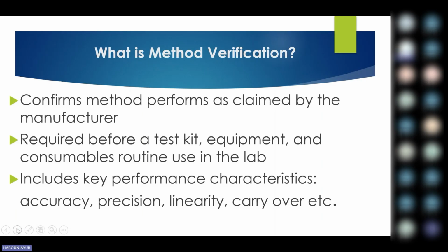If you get a patient with very high, let's say, viral load, what have you done in your analyzer to ensure that the same is not replicated to the next sample? You find different manufacturers will have different techniques in ensuring that this is done correctly. A will be single-use pipettes. B, manufacturers can adopt dual pipetting systems. Manufacturers that are using single pipette systems may be utilizing a double wash procedure, where they'll have a wash-in well and a wash-out well procedure. Manufacturers can also implement this by using Teflon.